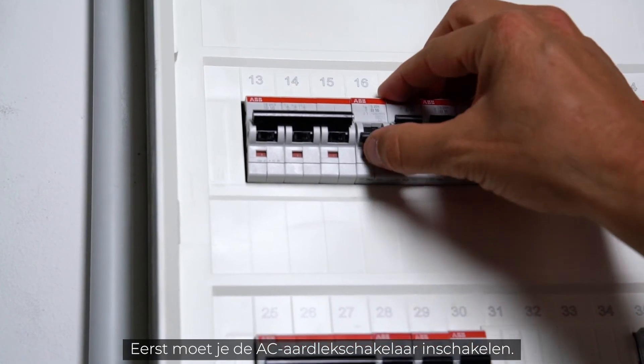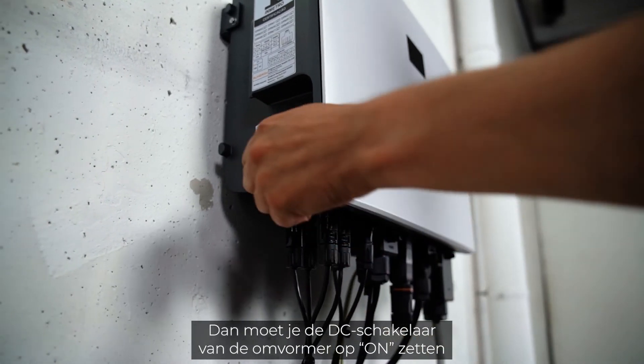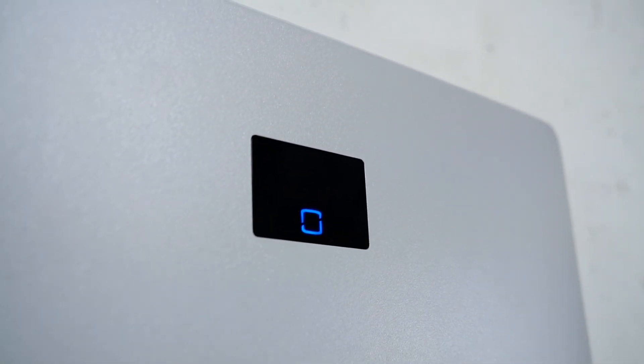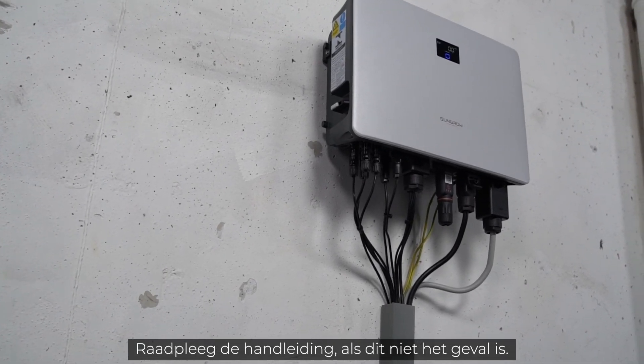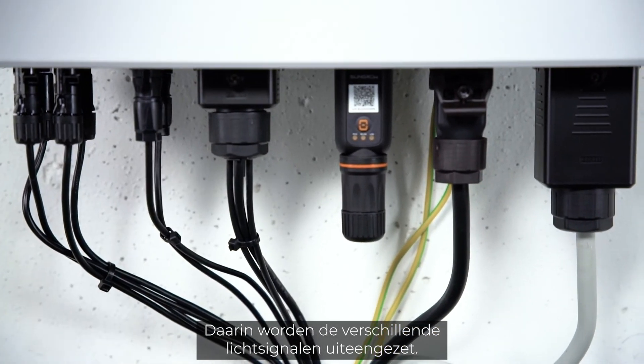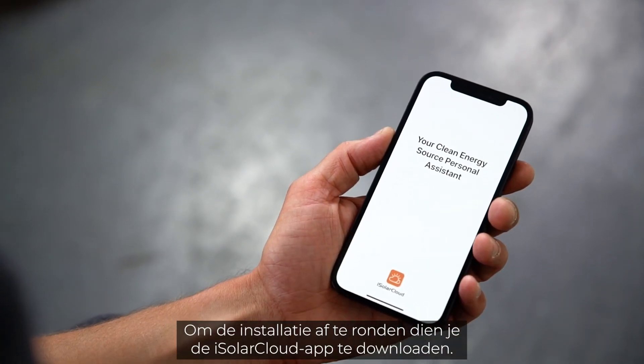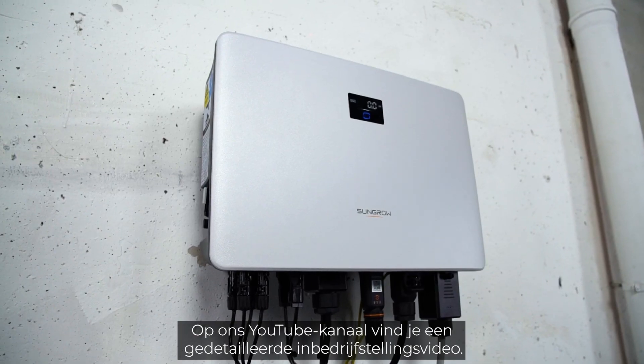Now it's time for commissioning. First, switch on the AC circuit breaker. Next, set the DC switch of the inverter to the on position to connect the inverter to the PV generator. A look at the LED light tells you if everything works properly — if the light shines continuously blue, the inverter is ready for use. If not, please refer to the manual for a breakdown of the different light signals. When connected, the WiNet module takes some minutes to fully boot. To finalize the setup, download the iSolarCloud app. A detailed commissioning video is available on the YouTube channel.